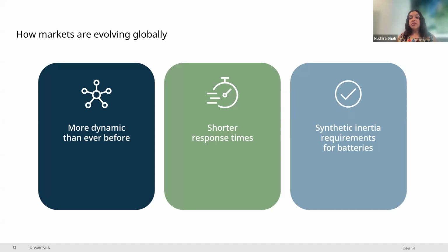When there's a big voltage change or frequency change, or a big generator trips, obviously inertia helps. So there's a question of, as we move to more inverter-based resources, how do we manage this grid stability issue? I think that about 10, 15 years ago, the idea was that batteries cannot do this. But then the industry came up with the idea that we could mimic the behavior of synchronous generators with software. Now there have been hundreds of publications on how to change the inverter controllers to provide synthetic inertia, mimicking that synchronous generator, and that's introduced a lot of benefits to grids and enabled grid stability in many ways.